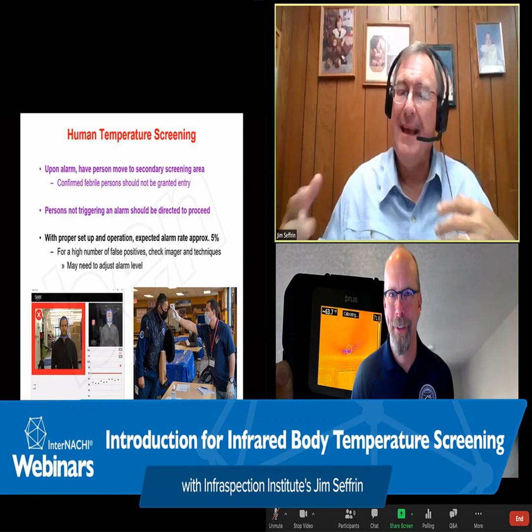A radiometer, also known as an infrared thermometer or a non-contact thermometer, is an electronic device that converts infrared energy emitted by an object's surface into a temperature value. Pictured here, we see a medical grade thermometer, and we're going to talk about the importance of the differences between industrial grade thermometers and medical grade thermometers as we evolve through our slides this morning. Last definition is an imaging radiometer. This is a thermal imager capable of measuring temperatures. Many of the infrared imagers that are sold to home and building inspectors these days are of the imaging radiometer type. They are thermal imagers that are capable of measuring temperature.